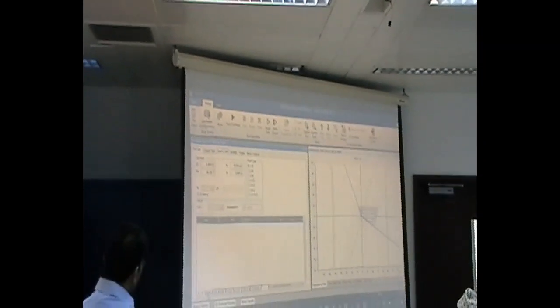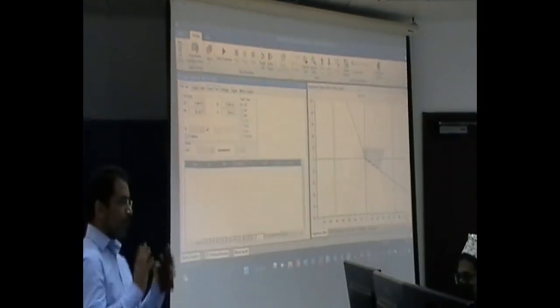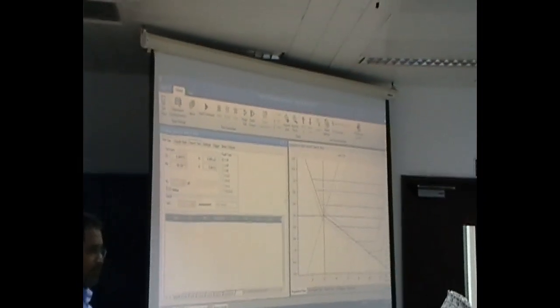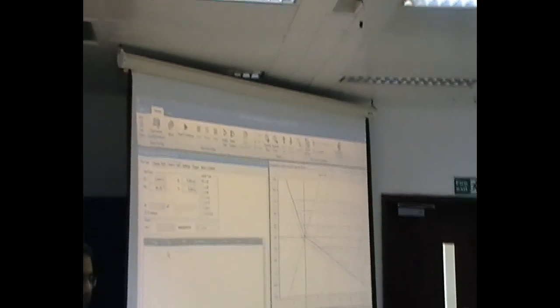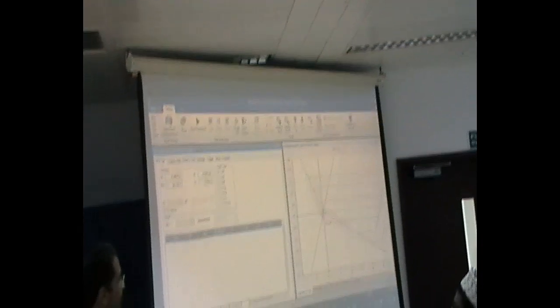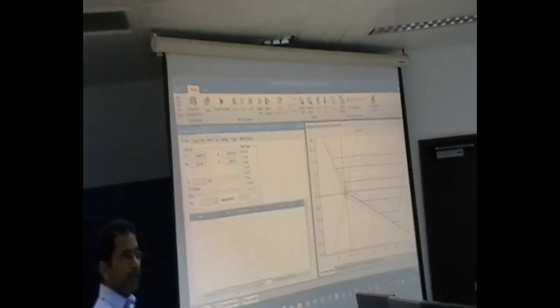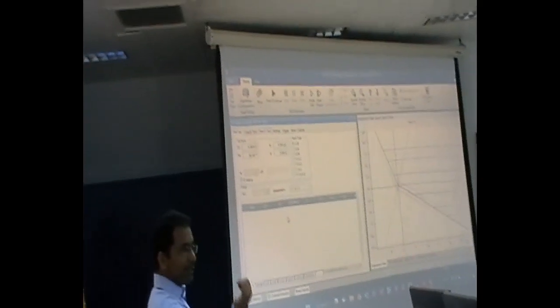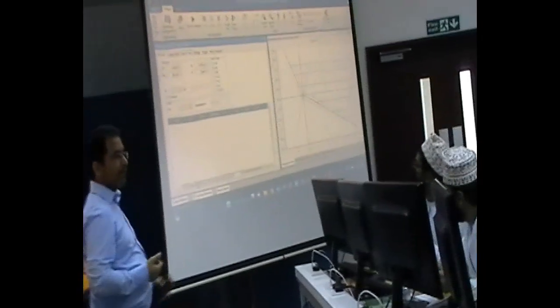This is the set. It's an Omicron CMC test set. This is the software of the Omicron test set that can be applied for any relay. Just extract the data from the relay, then put it here, then they will check each zone separately. The test set will inject the currents to the relay and receive the signal.